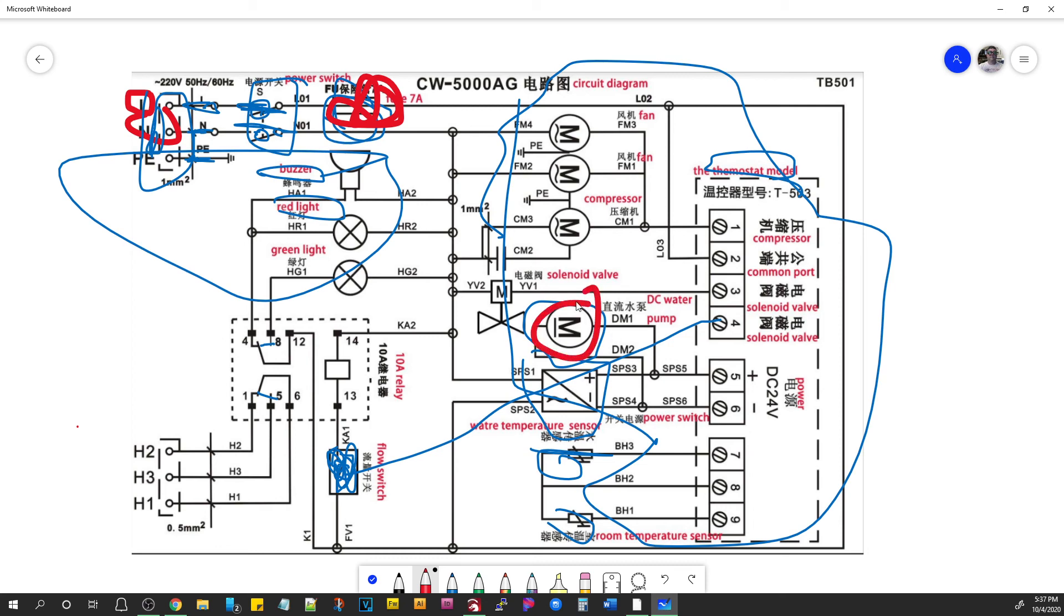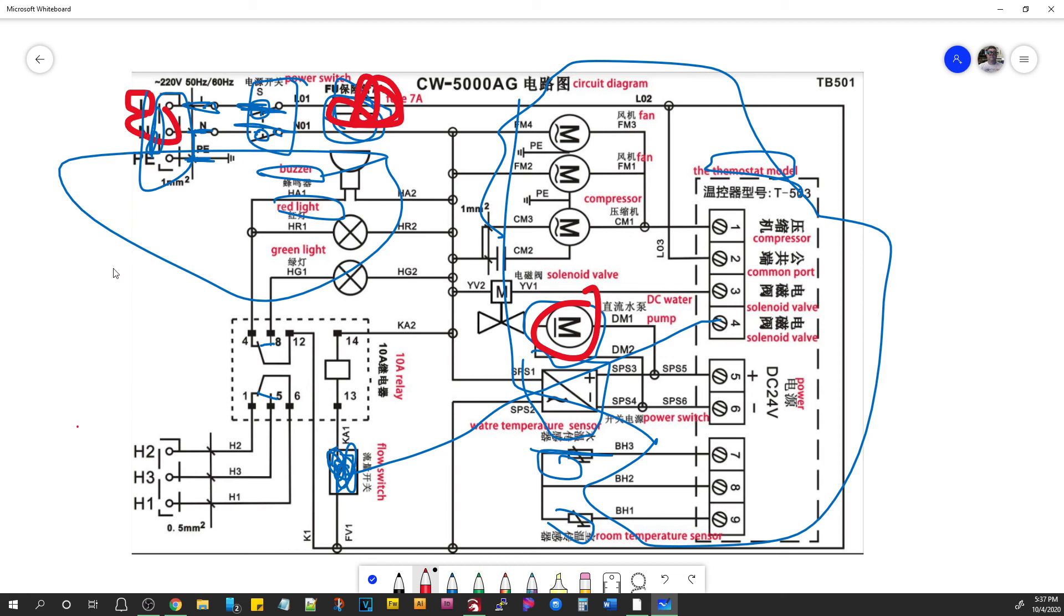Make sure your water pump is not impeded. You can go to your inlet and outlet on the back of the chiller, take a short section of hose and connect those. Turn your chiller back on and see if your error state goes away. That's one way to check the system just by looping the inlet and outlet on the back of it with a short piece. And turn on your chiller and run it and see if your problems go away. If they do, then you probably have a blockage somewhere in the laser tube or in the cooling lines or something like that. So that's a diagnostic thing you can try.